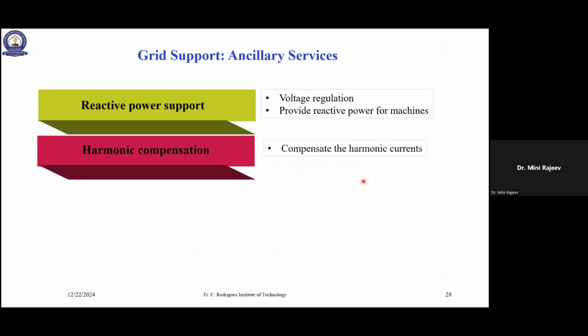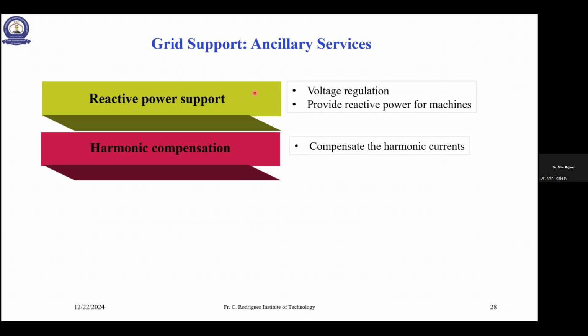Reactive power support, as I said before: instead of active power, you can feed reactive power to the grid if there is a voltage sag or anything. Voltage regulation, and providing reactive power for machines so that the grid is free from supplying it. Then harmonic compensation: the PV inverter can compensate the harmonic currents, so again the grid will be free from supplying these harmonic currents.